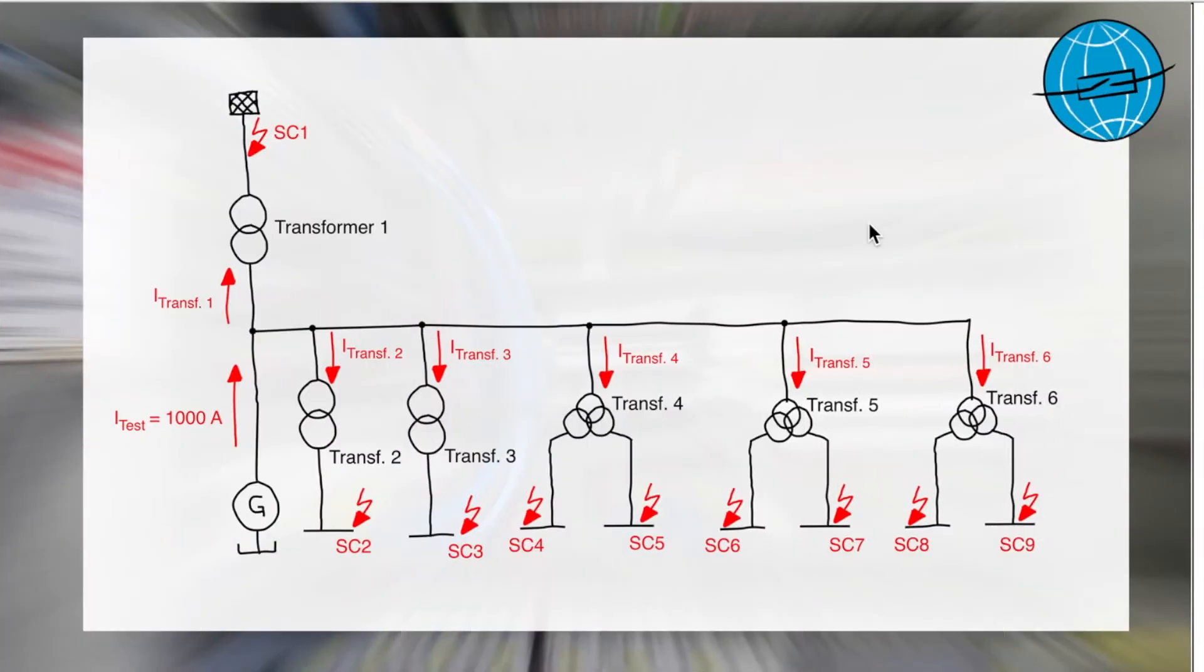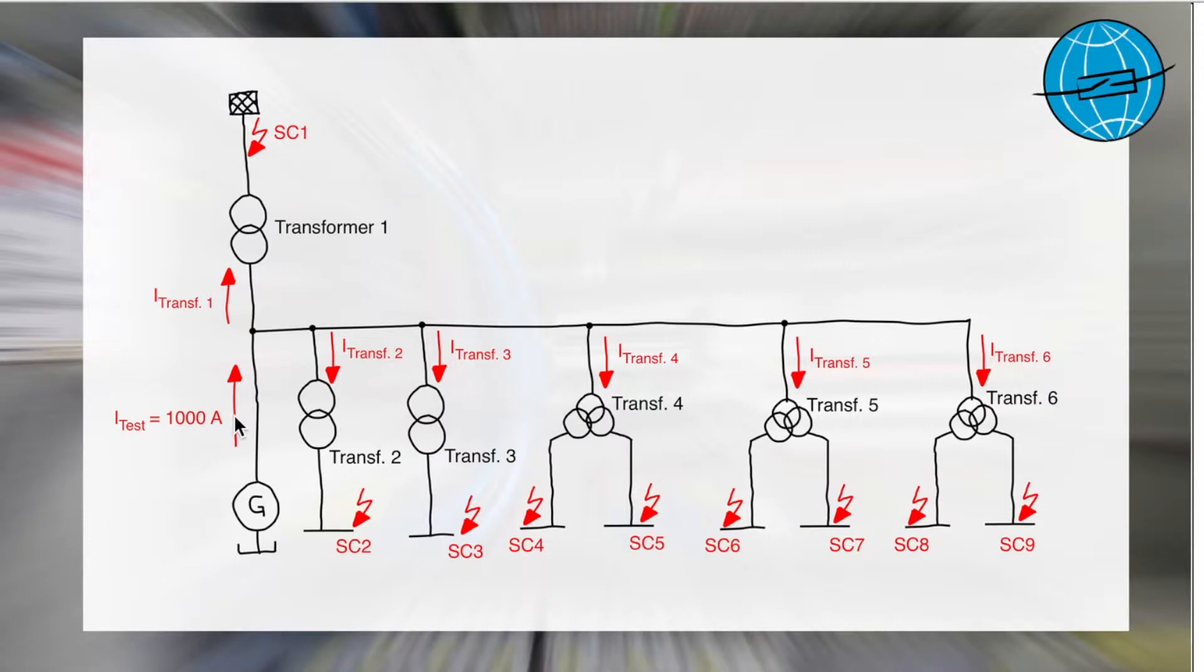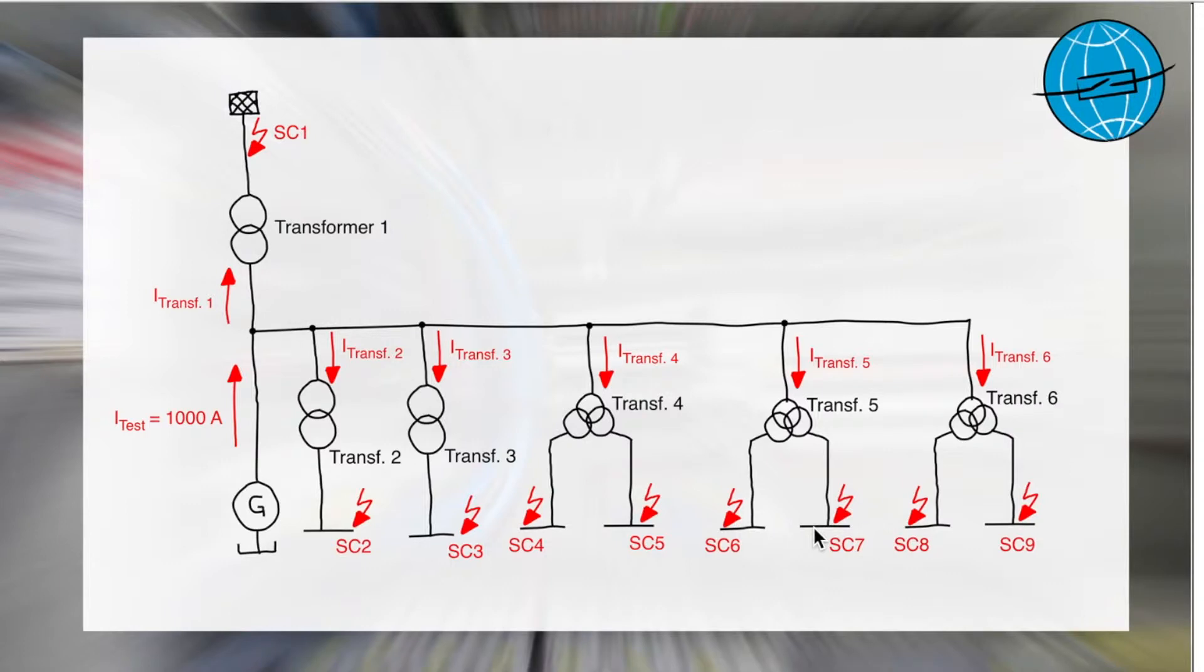Let's look first at the picture. We see a generator feeding a test current into the system. The connected transformers are three-phase short-circuited and grounded on the secondary sides. In sum, we have the opportunity to calculate the current distribution for up to six transformers.